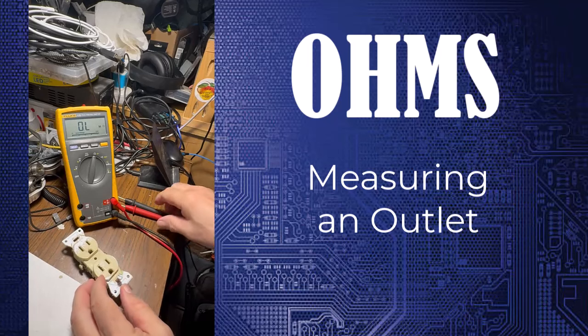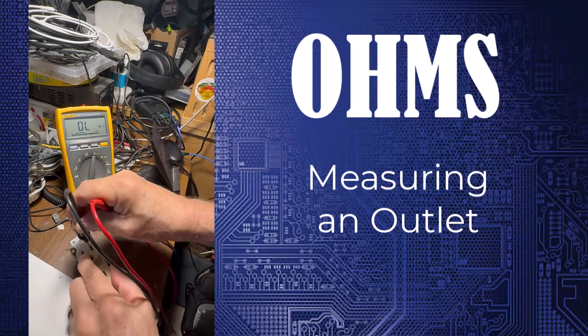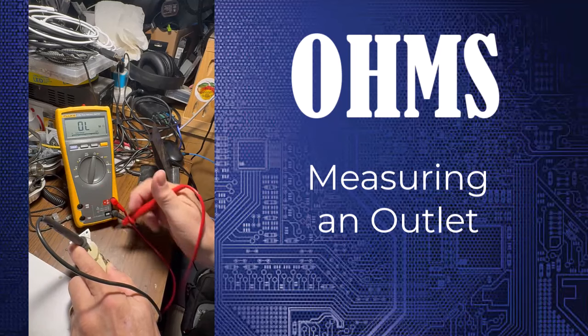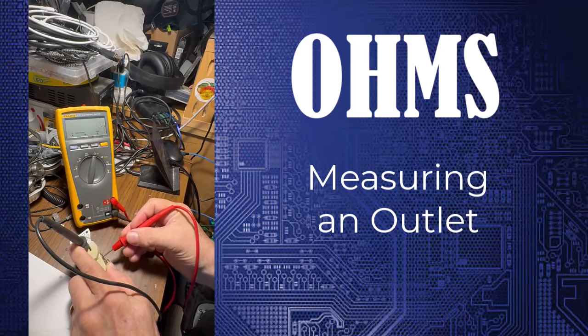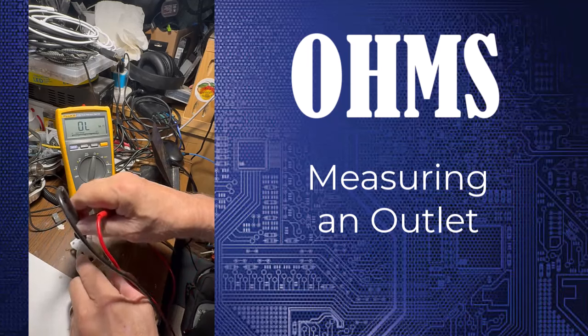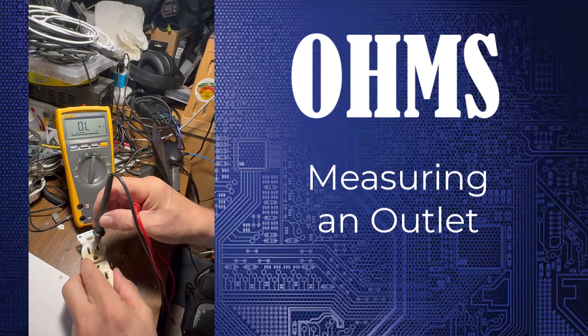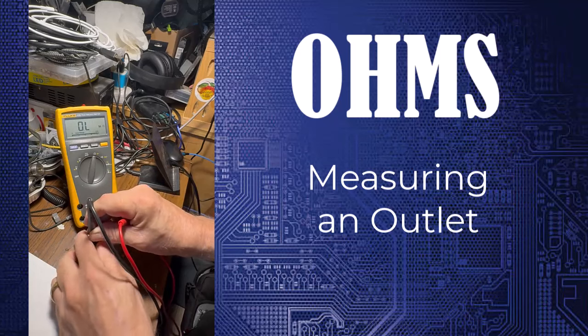Let's see if this outlet is good. First, place a probe in the small slot. It does not matter which slot you start with, I just chose this one first. Now take the other probe and touch it to the terminal screw. If the outlet is good, the meter will read near 0.